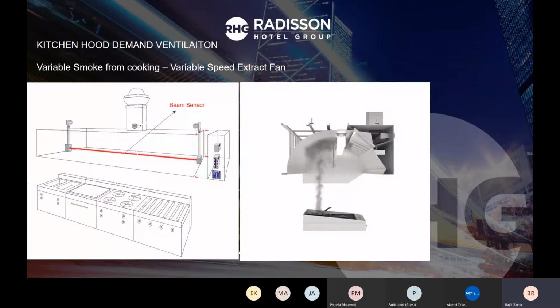I'm going to start sharing some practices of this sustainability third scenario, or the model, which is the variable. Here we can see we have a kitchen line, like your cooking range, burner, hot plate, etc. And I have the extract fan. In the previous model, we used to have a constant flow of extract through the duct and the hood, and extract the air outside. When we start the kitchen, let's say at 10 a.m., we run the fan on, and it's all the time extracting the same amount and the same flow of air.